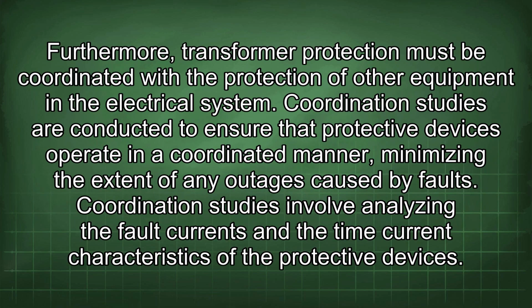Furthermore, transformer protection must be coordinated with the protection of other equipment in the electrical system. Coordination studies are conducted to ensure that protective devices operate in a coordinated manner, minimizing the extent of any outages caused by faults. Coordination studies involve analyzing the fault currents and the time current characteristics of the protective devices.